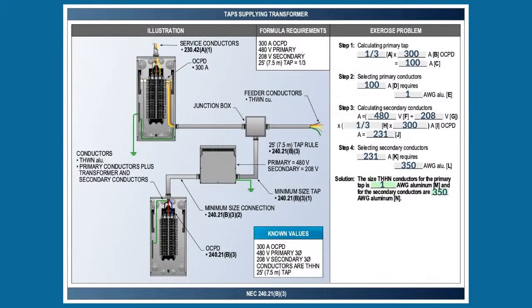And we did this on purpose. If you notice on the secondary, when you're looking at this, because this comes from the journeyman, we're always trying to make you think of how you're going to go about doing calculations. We threw a little trick in there this time, and we put aluminum conductors there. So now you've got to look over to the next, let's see, that'd be 1, 2, 3, the 5th column over in the 75°C column, and then you know you need at least an aluminum conductor that's 350 kcmil.